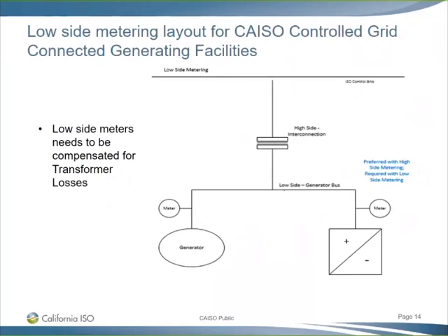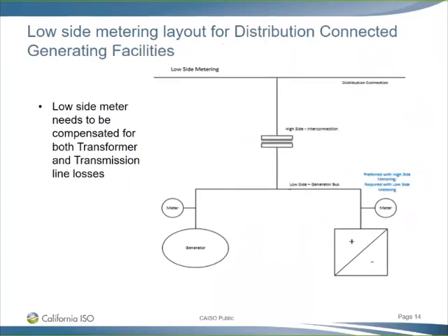The next scenario is for low-side metering, where there are separate meters for the on-site generator and for the storage unit. Both meters are connected at the low side, and in this case both meters have to be compensated for the transformer losses. Since the resource is connected to the grid, only transformer losses are required to be programmed in these two meters. In the last scenario, where the resource is connected at the distribution level and the meters are at the low side of the transformer, both meters have to be compensated for the transformer and also for the transmission line losses. Before we move on to the AC and DC connections, do you have any questions related to these four scenarios?